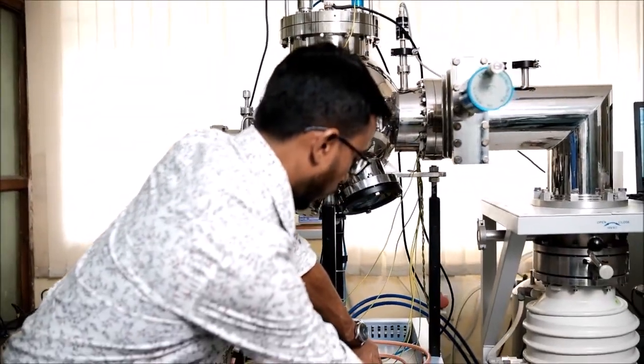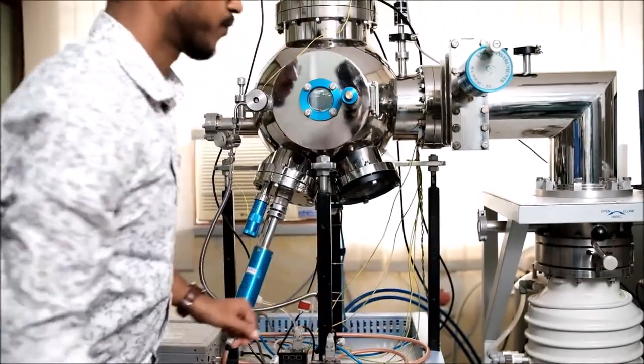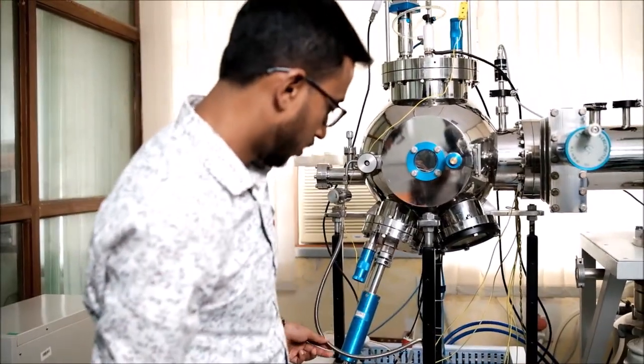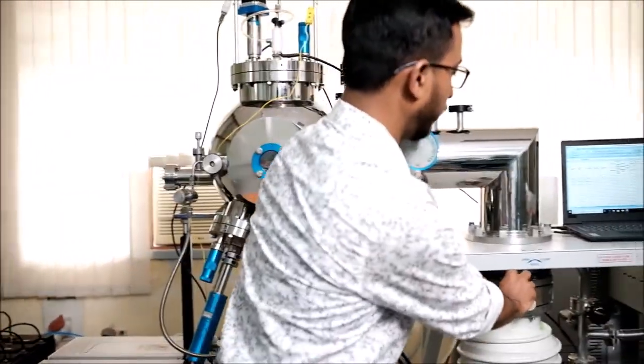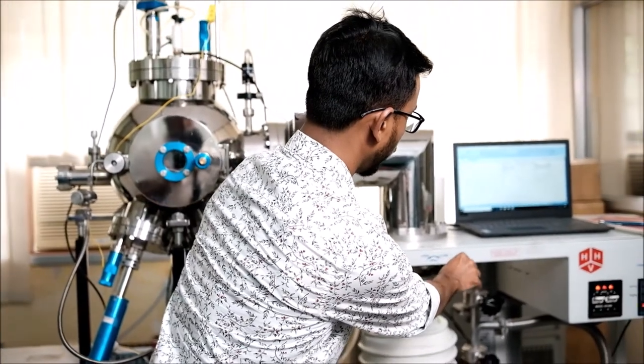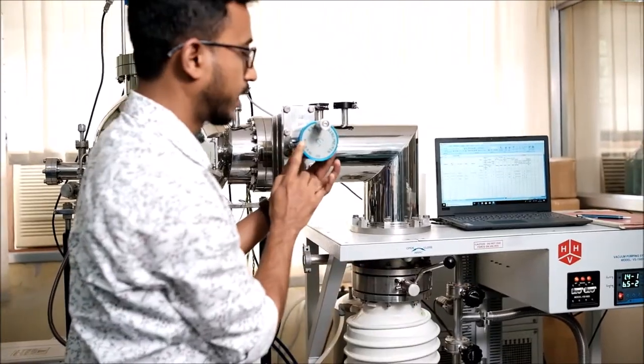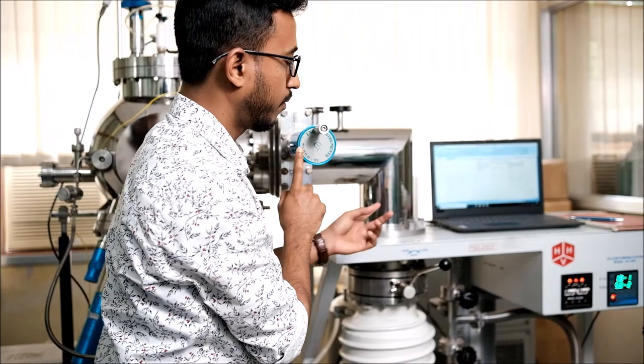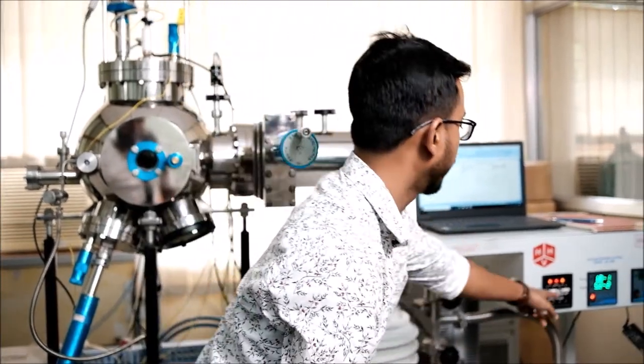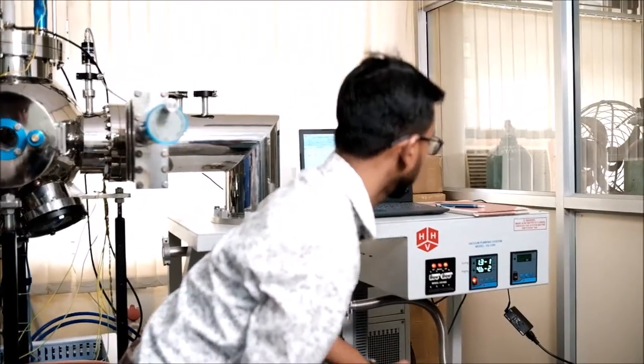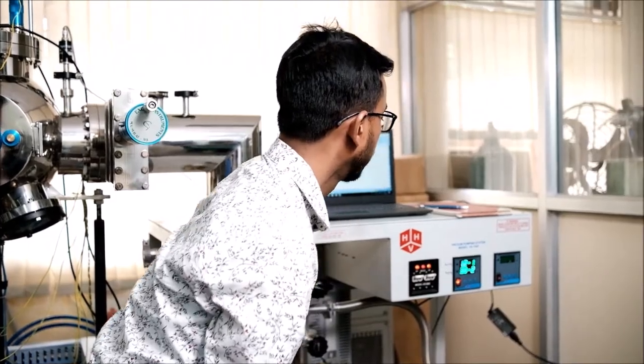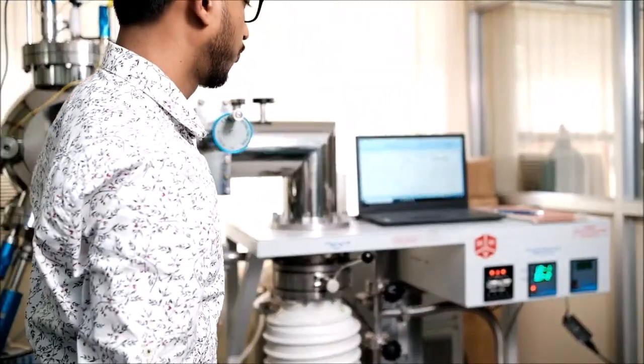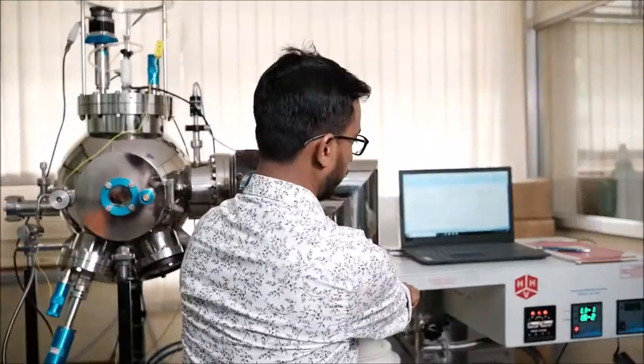So now we'll turn this to the ball valve. Okay. And then with the help of this butterfly valve and this gate valve, I will maintain the pressure of the chamber to 6.6 into 10 to the power minus 3 millibar. That is roughly around 5 millitorr of pressure.